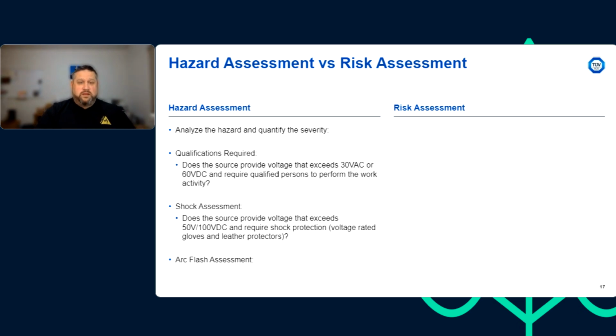If it's greater than our shock hazard threshold, which could be 50 or 100 volts depending on what you're applying for DC, then we have to have the proper PPE for that shock hazard, which is our voltage-rated gloves and leather protectors. And if we exceed 150 volts, we have to perform our arc flash assessment, and then wear the appropriate arc-rated PPE, which we'll cover in a second. So we can quantify it based on those things.